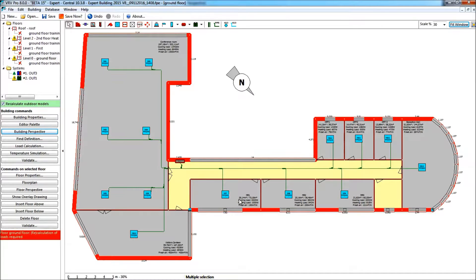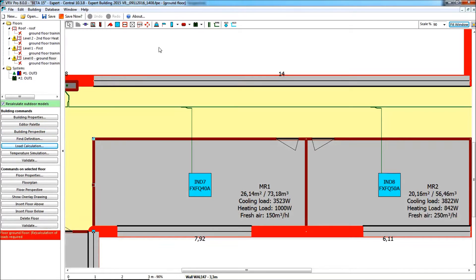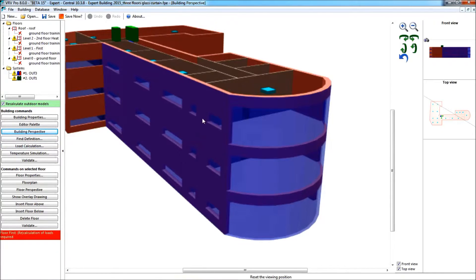Obviously this will have a result on the load calculation. Without the glass curtain we had 3523 W; after making a load calculation with the glass curtain, this goes down to 3498 W — some watts saved that will not affect the load of the room. When we have the three floors here, that glass shield around the building will positively affect the amount of solar radiation that hits the room and creates our load.